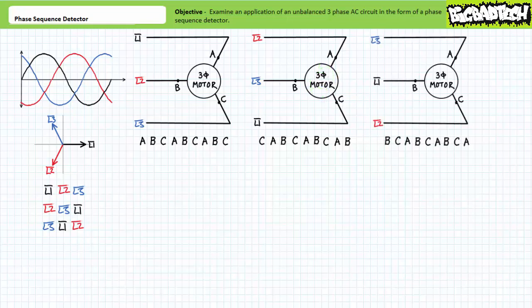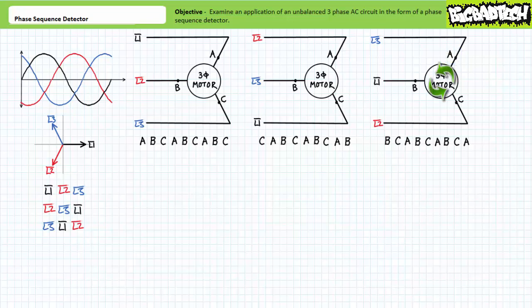Similarly, if phase L2 gets off the bus and L3 and L1 each move forward one seat, and L2 gets back on the bus and takes a seat in the rear, again not much has changed regarding the sequence — only the starting point within the same sequence. As L1 voltage peaks it establishes a magnetic pole at terminal B, then as L2 voltage peaks at terminal C, then as L3 voltage peaks at terminal A. The process repeats itself, BCA, BCA, again establishing counterclockwise rotation.